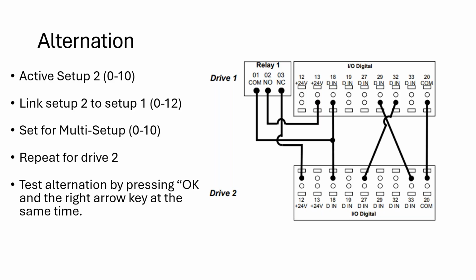Alternation. So this is like we were just talking about having a backup pump. You can also do some wiring and active setup. I'm not going to get into these too much, but it'll alternate, right? So you run pump 1 for 3 days, and then you run pump 2 for 3 days, and each one's a backup to the other. That way, you're helping the longevity of both of the pumps. So you can do that with this drive as well. I don't think anything that I'm mentioning here is way out of whack.